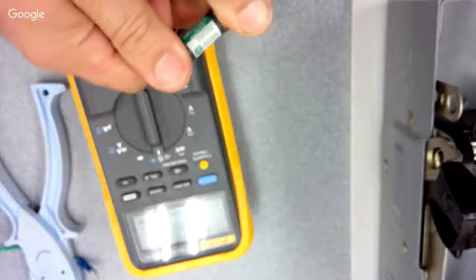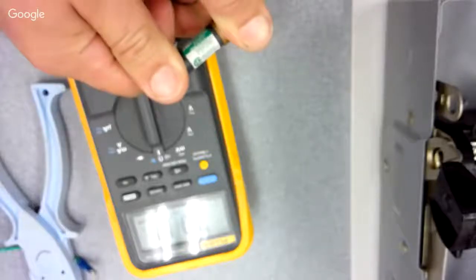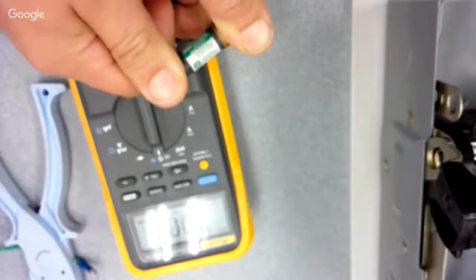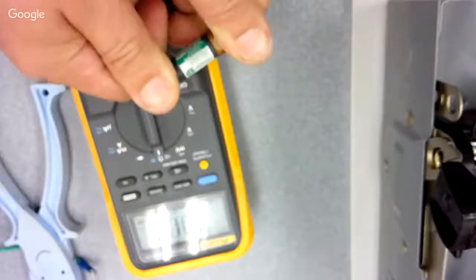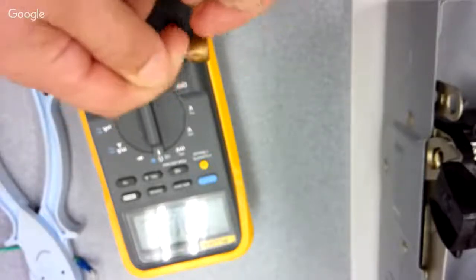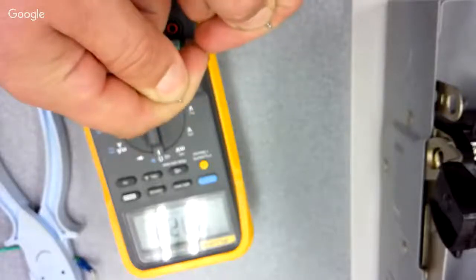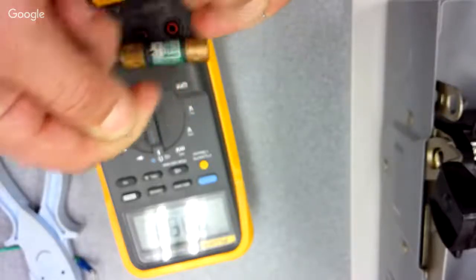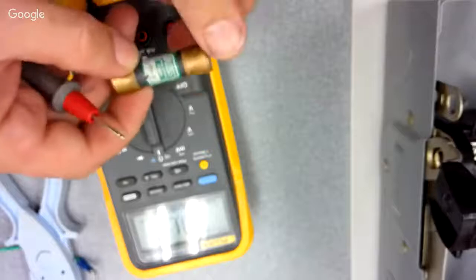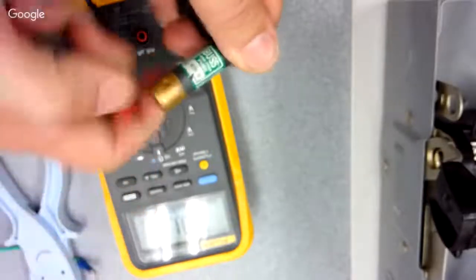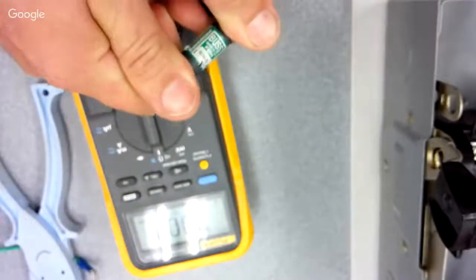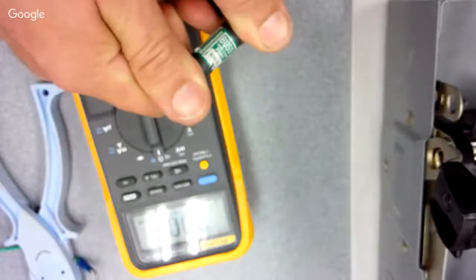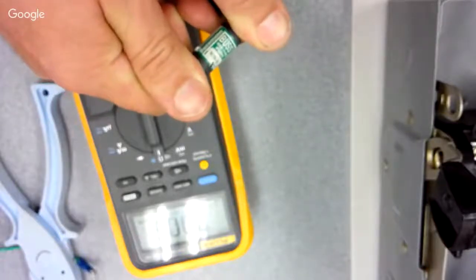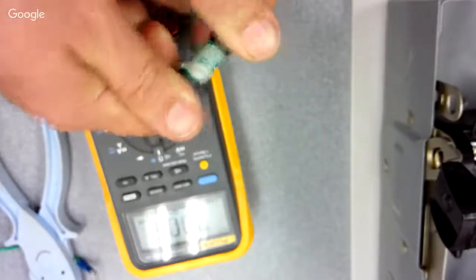One of the things you need to watch out for is on an auto range meter, you will get a reading if I just hold it in my fingers, right? I'm getting mega ohms. That's no good. That is the resistance of my body right now. So you need to pay attention to the number. You should be down here on the ohms level, not on kilo ohms or mega ohms, or just on ohms. And so that fuse is good.